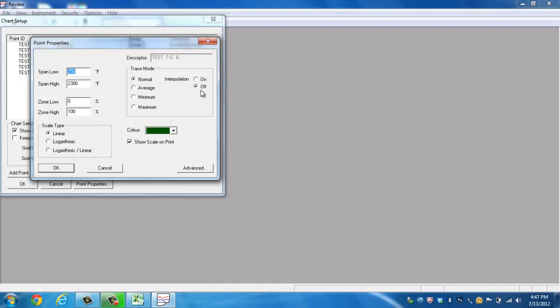So when you do an average, it's going to take the points that happen during that pixel. For example, if you're zoomed in at 1 second interval, a pixel might be 1 point of data, one data read. But if you zoom out for 10 points, that may be 2 or 4 or 5 points of I/O. So what it's going to do is take all those reads and average them together.